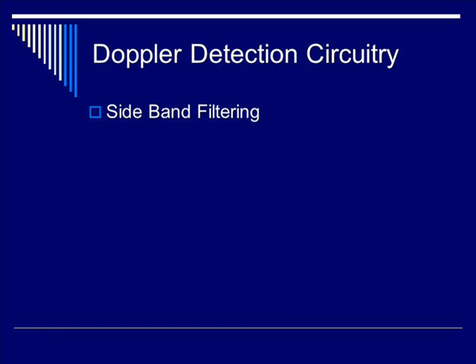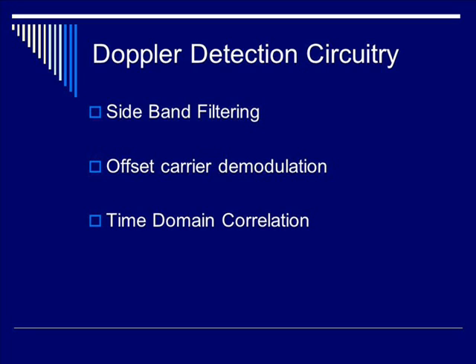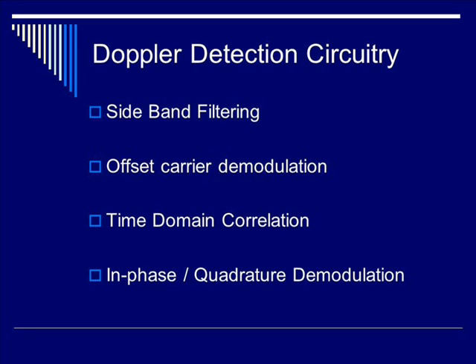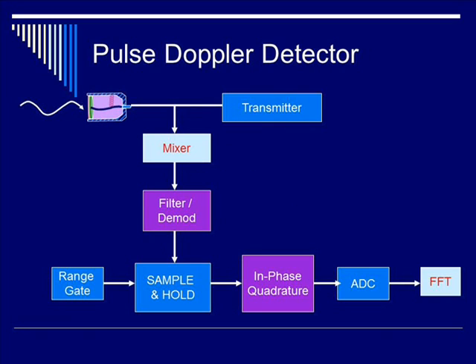Let's talk about the Doppler detection circuitry. Over the years there have been multiple implementations, such as sideband filtering, offset carrier demodulation, time domain correlation, and finally in-phase quadrature demodulation. For all practical purposes, you just need to know about in-phase quadrature demodulation, because that's what's used today. The pulse Doppler detector circuitry is similar to the continuous wave circuitry, with the exception of a sample-and-hold, quadrature, and the FFT.